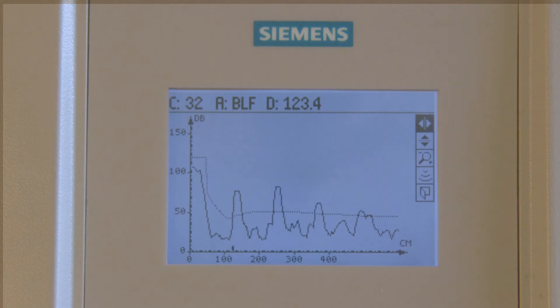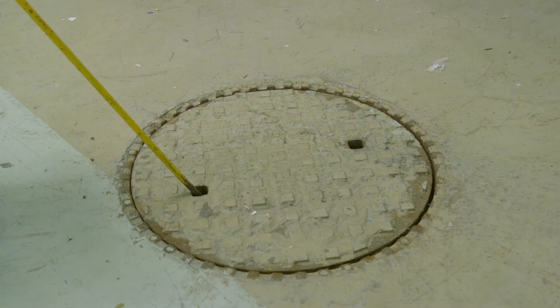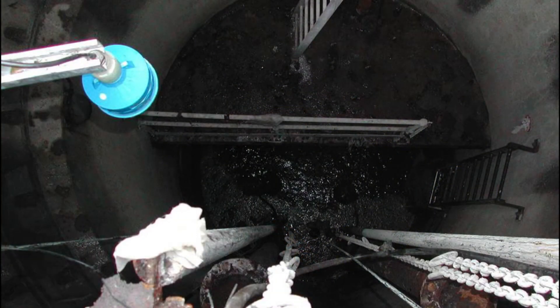This example shows multiple echoes that cross the threshold. From this profile, it's not clear which echo is the actual material echo. Based on the product's default echo processing parameters, the device has picked this echo. It is clear that there are obstructions in the tank causing that echo. So how do we get the sensor to read the correct distance?